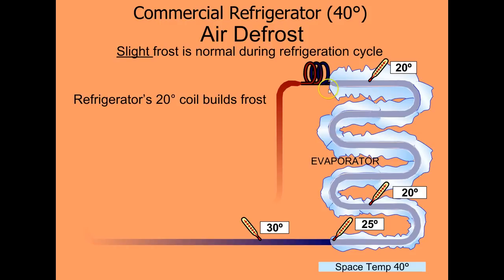In this instance we have proper refrigeration happening, frost is building up on the evaporator coil, and we do have 10 degrees of superheat.